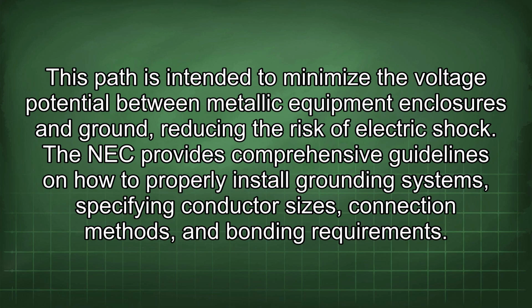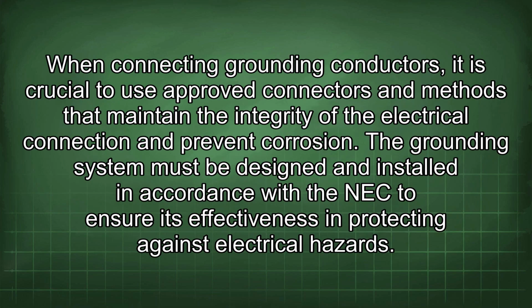The NEC provides comprehensive guidelines on how to properly install grounding systems, specifying conductor sizes, connection methods, and bonding requirements. When connecting grounding conductors, it is crucial to use approved connectors and methods that maintain the integrity of the electrical connection and prevent corrosion. The grounding system must be designed and installed in accordance with the NEC to ensure its effectiveness in protecting against electrical hazards.